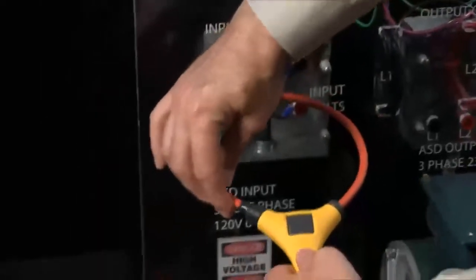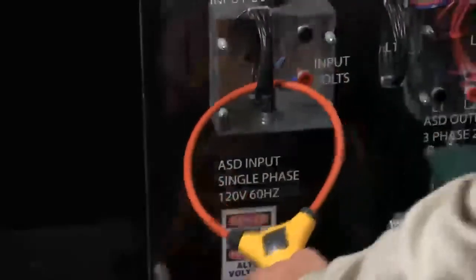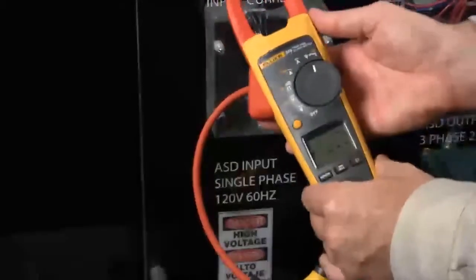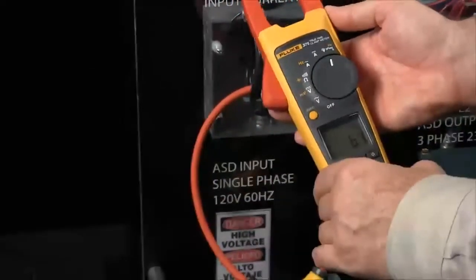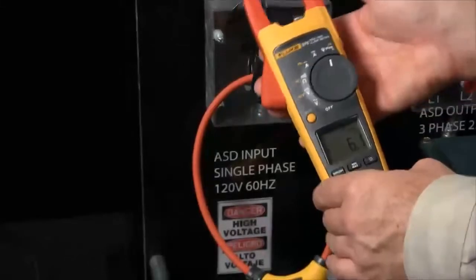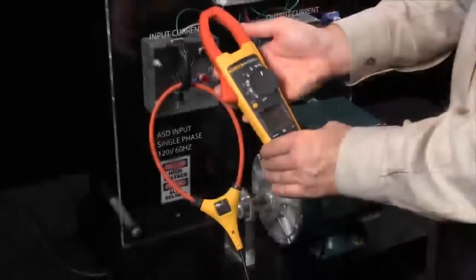Simply loop the iFlex around your conductors and change the setting on your dial to read through your iFlex. You're reading your current through the iFlex as opposed to the molded case.